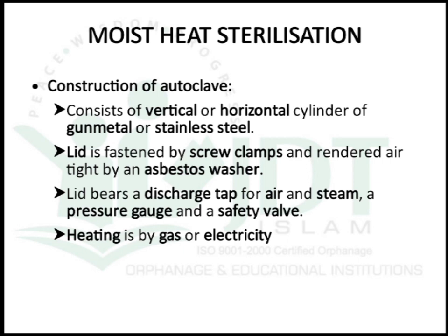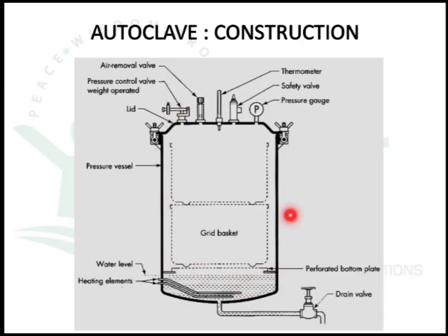The autoclave may be either vertical or horizontal, made of gunmetal or stainless steel. It has a lid fastened by screw clamps and rendered airtight by an asbestos washer. The lid bears a discharge tap for air and steam, a pressure gauge, and a safety valve. Heating is by gas or electricity. A vertical autoclave has a heating element, a perforated bottom plate above it, and a grid basket above that for placing materials to be sterilized. The lid consists of an air removal valve, a thermometer, a safety valve, a pressure gauge, and a screw cap.